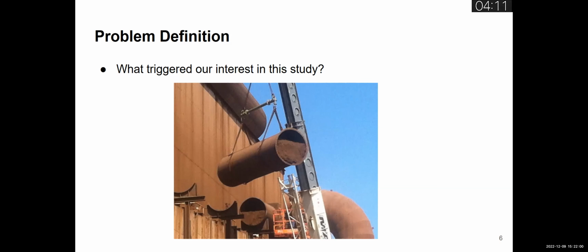There are a few problems identified by industrial hygienists in this work environment. As you can see in the picture, there is an industrial ventilation duct filled with material. It should be perfectly clean. We have this problem even though the systems are being designed with the traditional method.